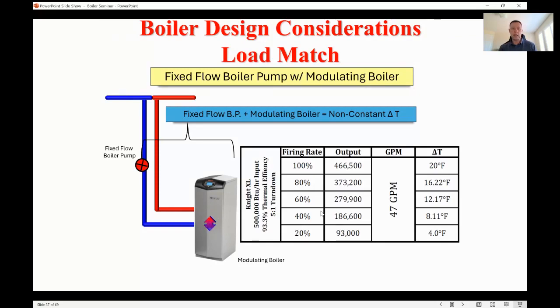So take a look. A standard primary-secondary, something like this, is modulating from 20 to 100% fire. In a standard situation with a static pump, as that boiler modulates down, the flow stays constant. So what happens? What changes? The delta T will change, right? You might have sized that as a 20-degree delta T at 100% fire, but as you ramp down, that delta T will lessen all the way, in this case, down to 4 degrees Fahrenheit at 20% modulation. And basically, that's what's happening with a static pump here.